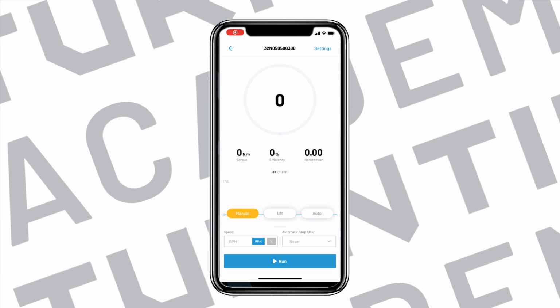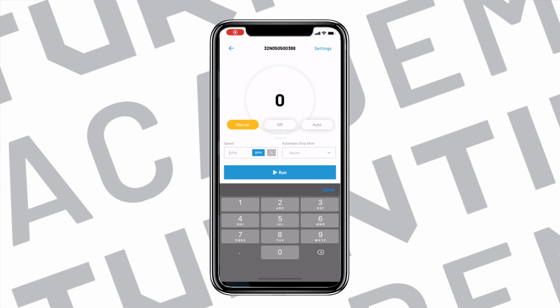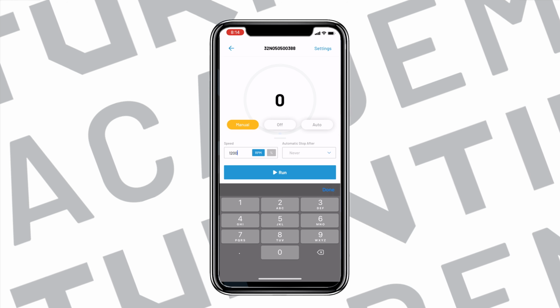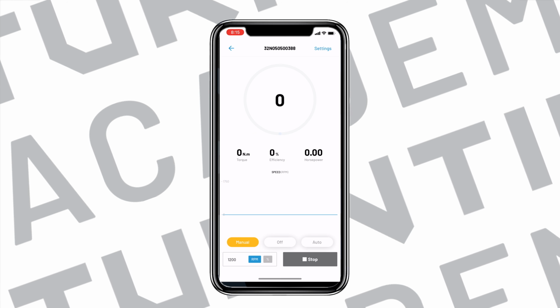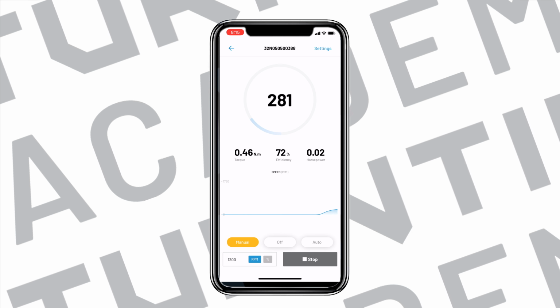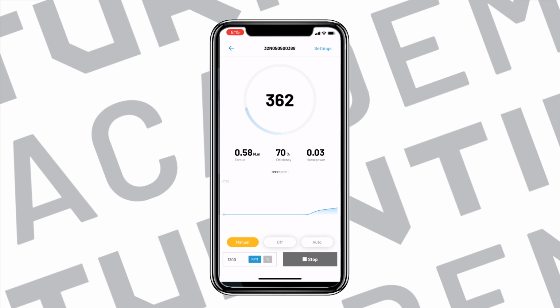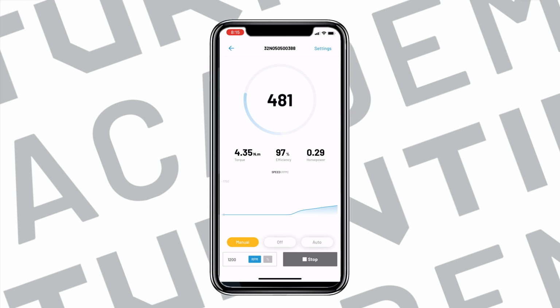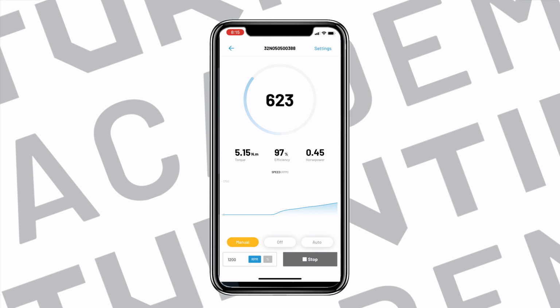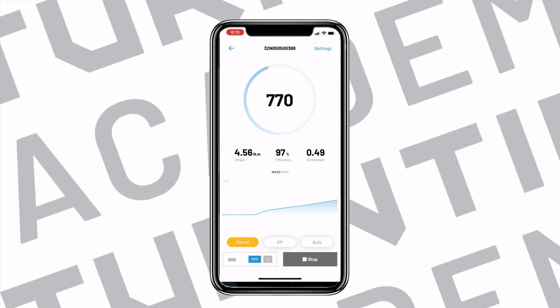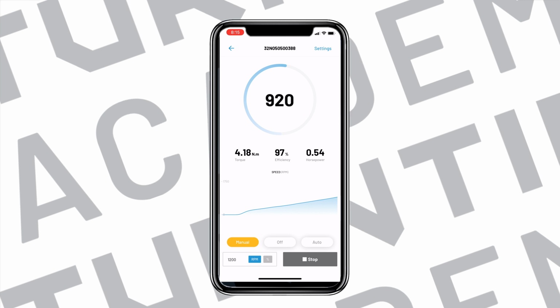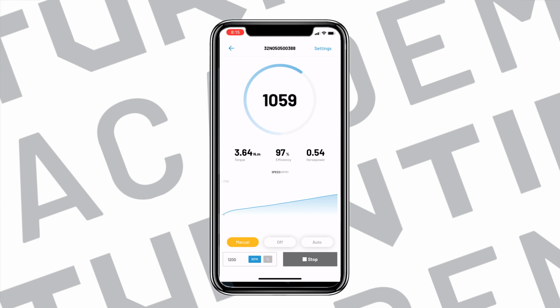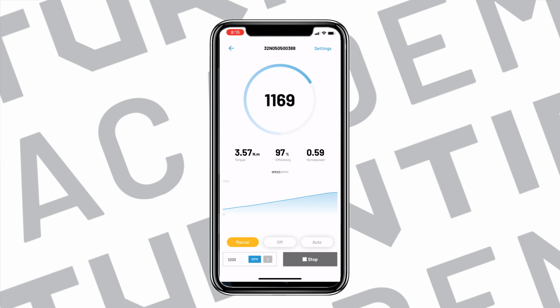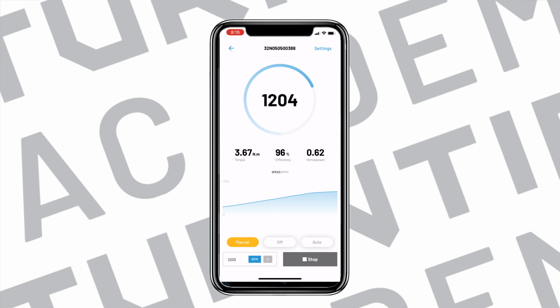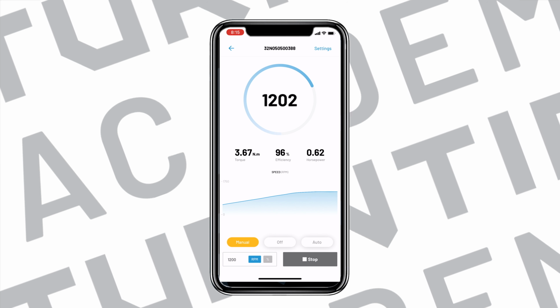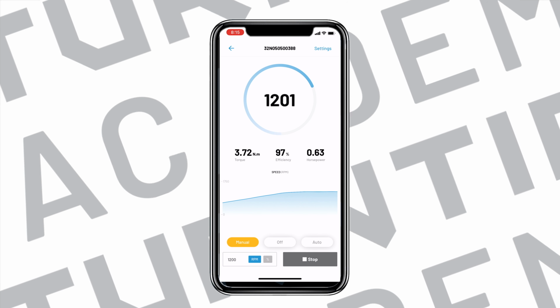Here there are 3 operation modes for the technician to choose from. Choose Manual and enter an RPM to confirm motor operation and rotation. Select Stop to exit the manual mode. Note that the manual mode only operates the motor system. The heating and cooling are not enabled by the manual mode. Once engaged, the manual mode will operate indefinitely.